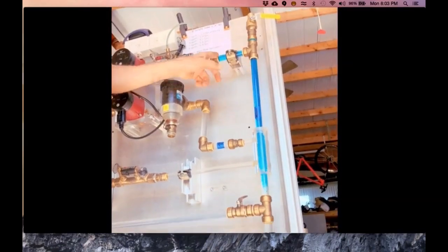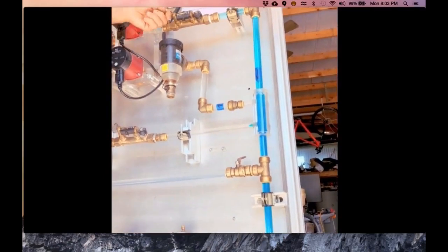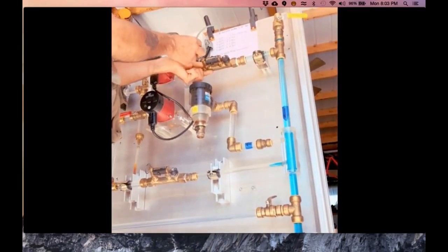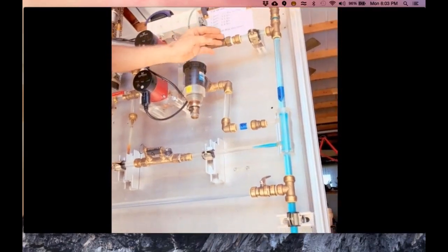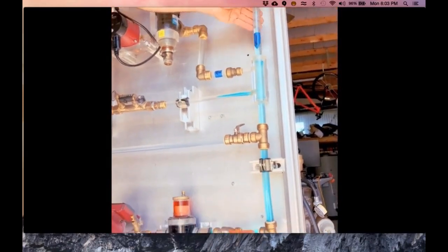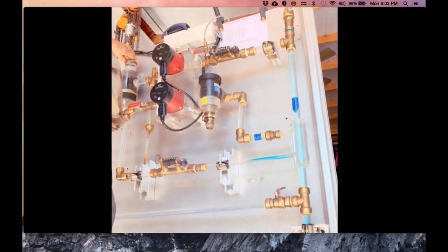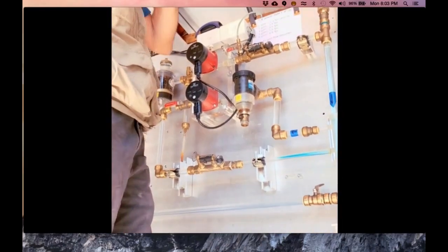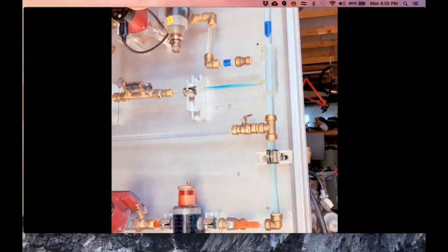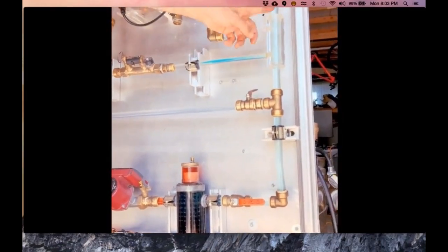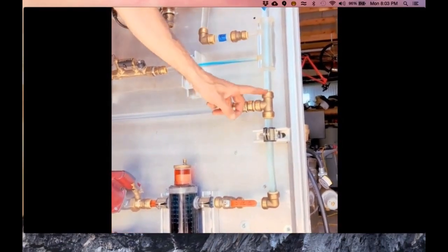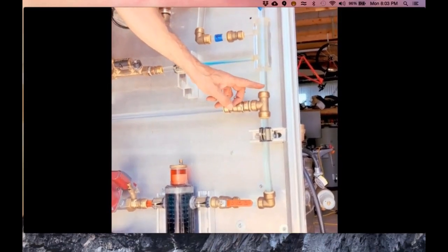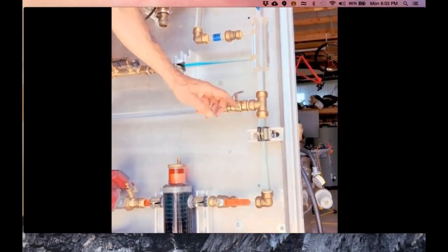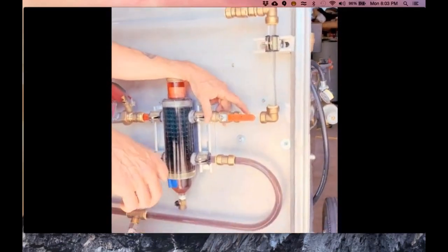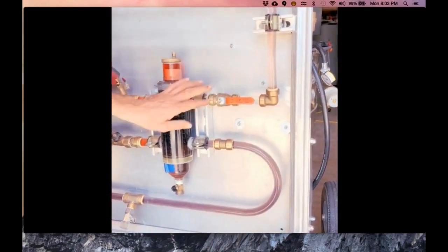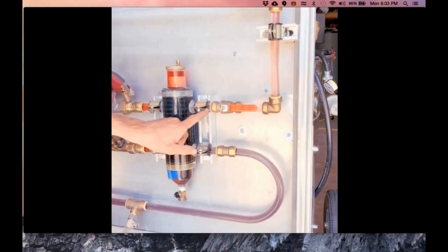Let's get this pump going here. So I'm going to come down here. Again, I'm going through about, let me see what it is, but it should be about 3 gallons a minute that we're going through there. And now the blue is going to come down. Give it a second here to blend a little bit, get a little bit of air out of there. Okay, the blue's making its way down. Probably could put a little more blue in there. You can see it's starting to come down through the primary secondary pipe. It'll make its way down to the separator. You can see the blue coming down here. Now you can see, obviously it's mixing with the red a little bit. That's why it's turning purple here.